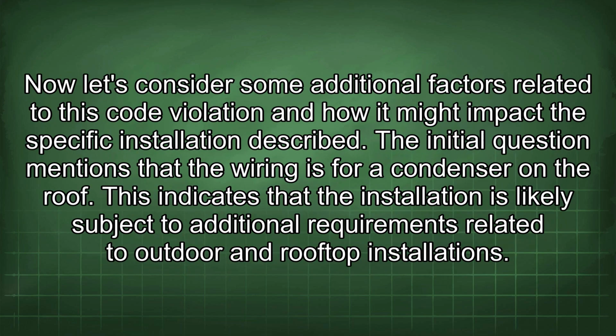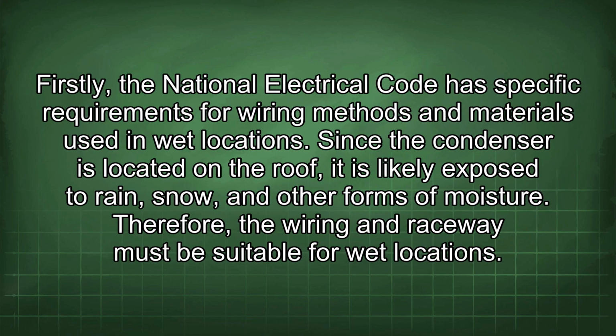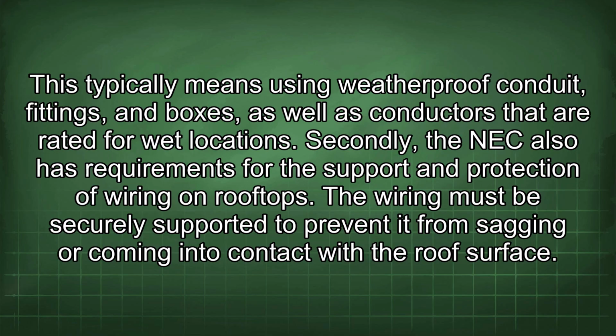Now let's consider some additional factors related to this code violation and how it might impact the specific installation described. The initial question mentions that the wiring is for a condenser on the roof. This indicates that the installation is likely subject to additional requirements related to outdoor and rooftop installations. Firstly, the National Electrical Code has specific requirements for wiring methods and materials used in wet locations. Since the condenser is located on the roof, it is likely exposed to rain, snow, and other forms of moisture. Therefore, the wiring and raceway must be suitable for wet locations. This typically means using weatherproof conduit, fittings, and boxes, as well as conductors that are rated for wet locations.